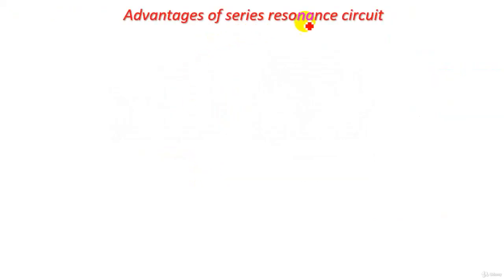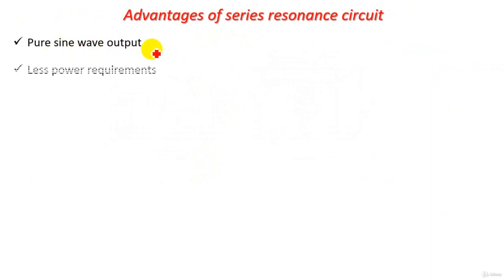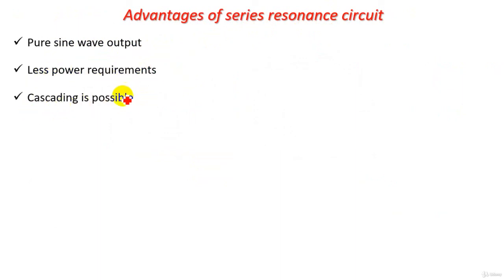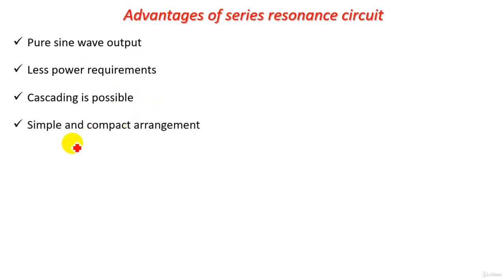Advantages of the series resonance circuit: First, a pure sine wave output is obtained with no harmonics. Second, less power requirements. Third, cascading is possible to produce very high AC voltage, and it offers a simple compact arrangement.